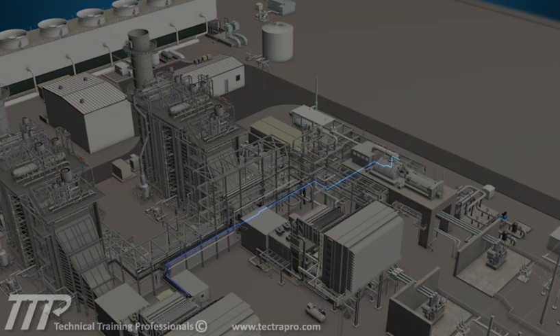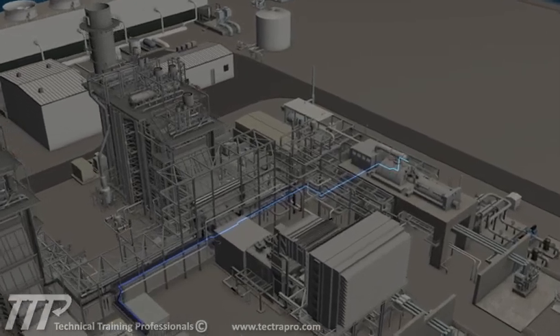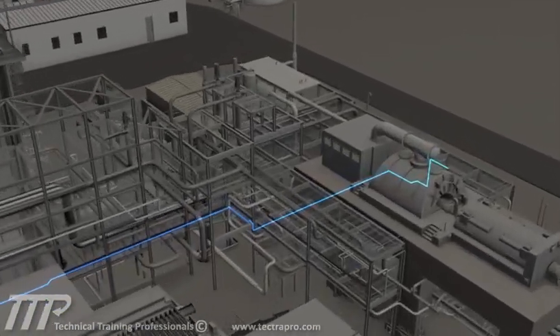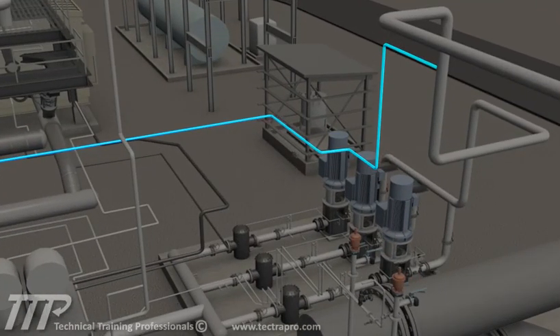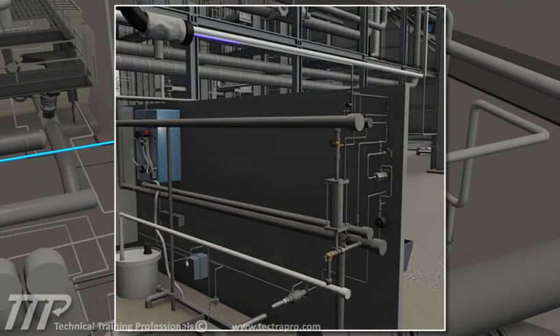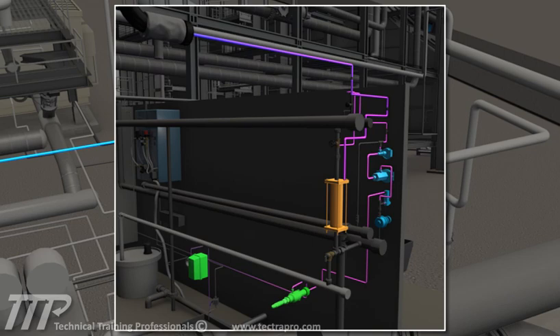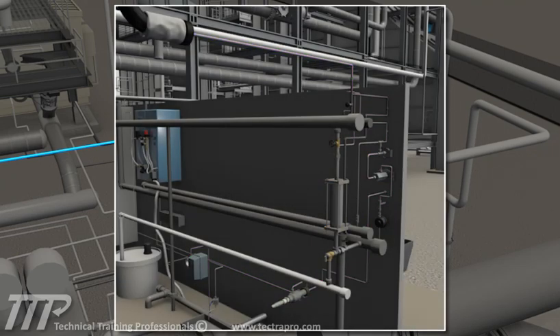Sample point 1 is the condensate pump's discharge. At the sample panel, the condensate is cooled and its pressure and flow are adjusted before flowing to the pH and specific conductivity analyzers. Provisions for manual sampling are available to further analyze the conditions of the water, for example, oxygen and iron content.